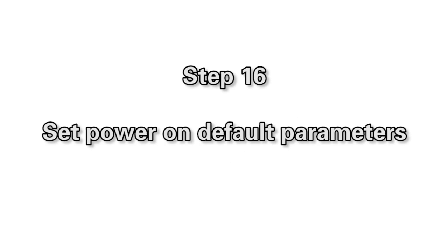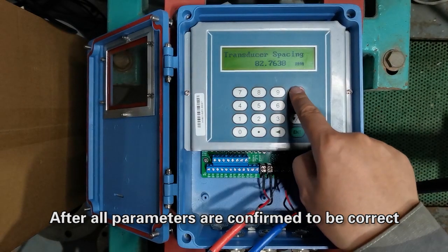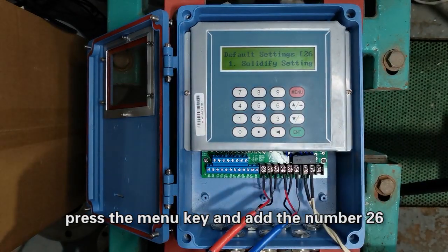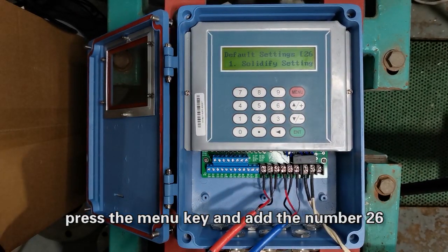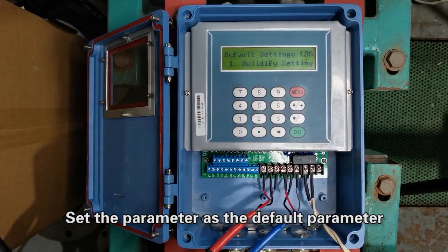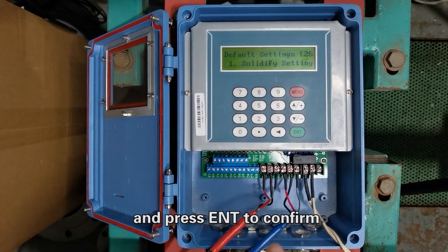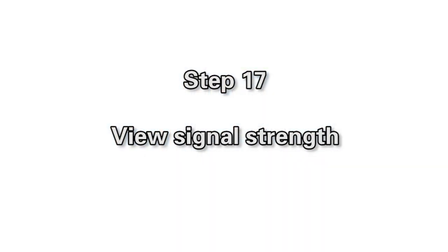Step 16. Set power on default parameters. After all parameters are confirmed to be correct, press the menu key and add the number 26. Set the parameter as the default parameter and press Enter to confirm. Step 17. View signal strength.